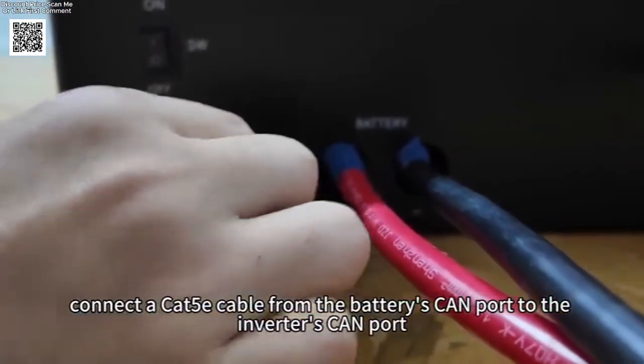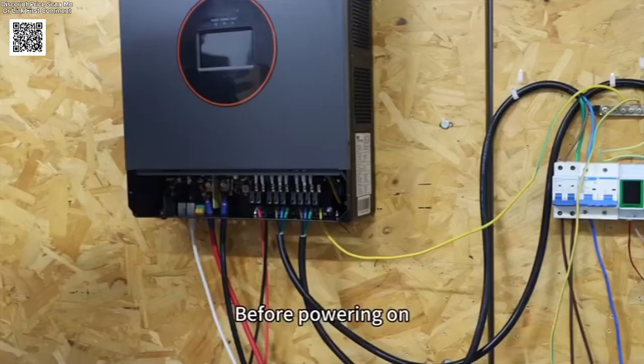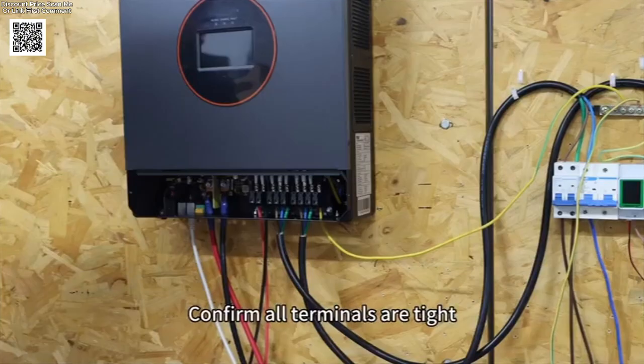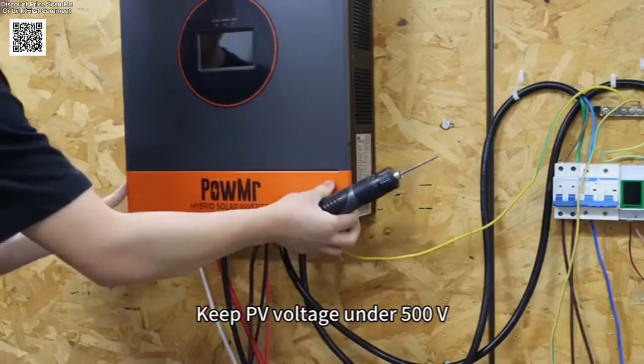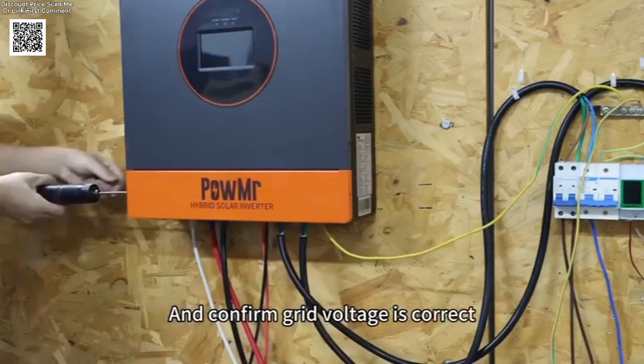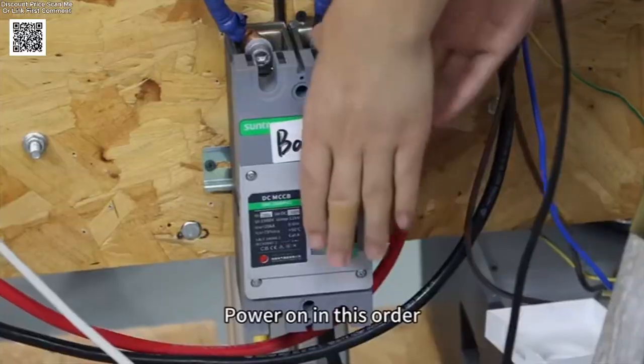Before powering on, check polarity on all connections, confirm all terminals are tight, verify breaker size, keep PV voltage under 500 volts, and confirm grid voltage is correct. Power on in this order.